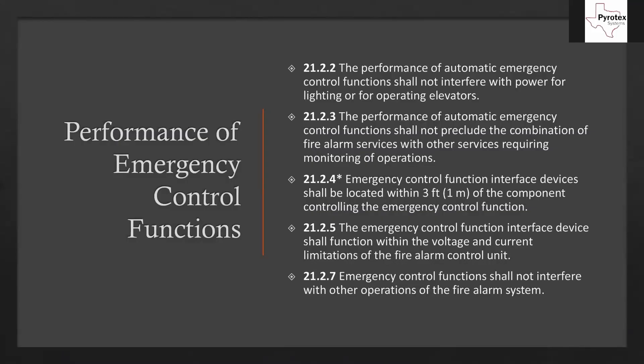A few performance points: the performance of automatic emergency control functions shall not interfere with the power for lighting or for operating elevators. The annex explains that under normal conditions — when there's not a fire or emergency — we don't want to interfere with normal elevator operation. There's a majority of this chapter that deals with elevator operation; we've done a previous video on it. Also, the performance of automatic emergency control functions shall not preclude the combination of fire alarm services with other services requiring monitoring operation — meaning the emergency control functions can't stop the fire alarm from doing what it needs to do.